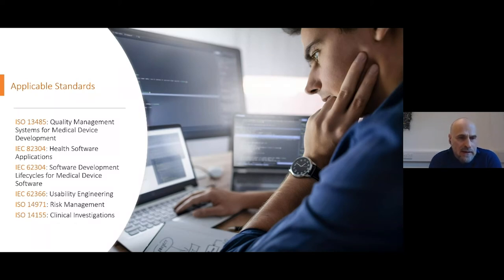IEC 62366 applies to usability engineering and particularly use errors, and involves developing an understanding of the types of errors that users can make and how that can result in hazards, and how those hazards are best managed through better user interface design. ISO 14971 is another key standard for risk management.